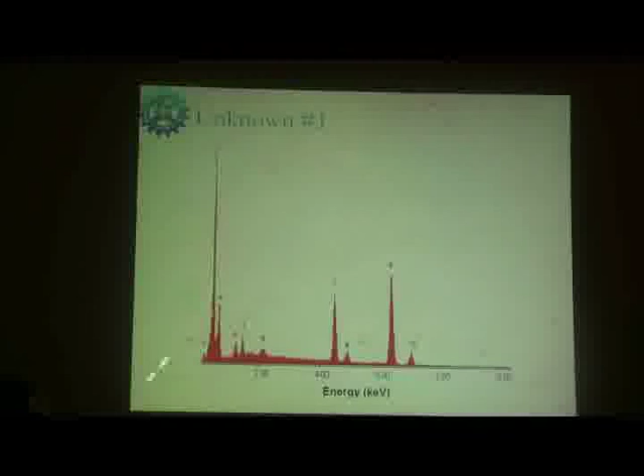You take phosphorus, atomic number 15, K alpha is 2.03, zirconium 40, L alpha is the same. And for iridium, M alpha is very close. So when you have energies like this, you can mistake whether it is phosphorus or zirconium or iridium. So when the energy levels are very close, it is very difficult to tell unless you look at the other peaks of that particular element.